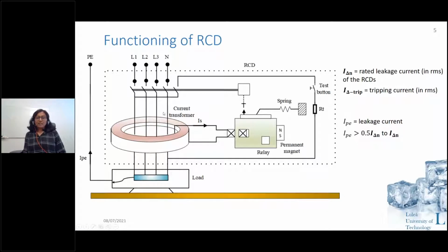So basically the current has to generate enough force to oppose the magnetic field of this permanent magnet. Standards define what this value of the tripping current should be. According to standards, the value of this tripping current should be anything between 0.5 times the rated current of the RCD and the rated current of the RCD. So this is a simple definition of an RCD.